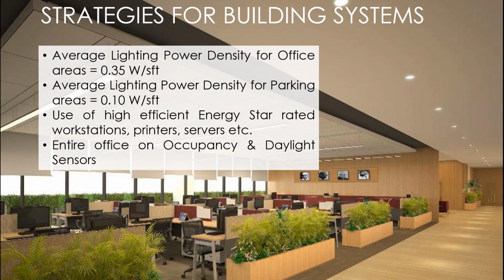Right. Then when we talk about lighting, which is the second major energy consumer, we all know we talk about office lighting. We started with 1 watt per square feet, 7-8 years back. It came down to 0.8, 0.7. Now, I believe the average is 0.5 to 0.6. What we are using here is 0.35, rather 0.32, is what we have achieved now, watt per square feet, getting an average lux of about 340 and a uniformity of 70%.